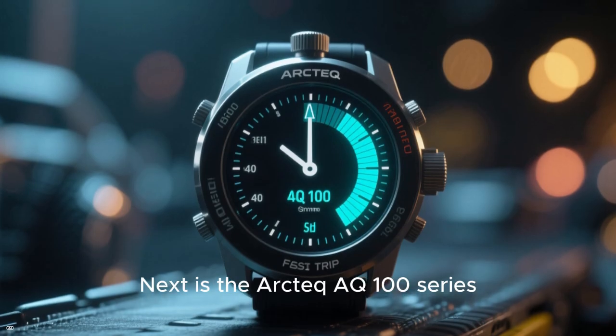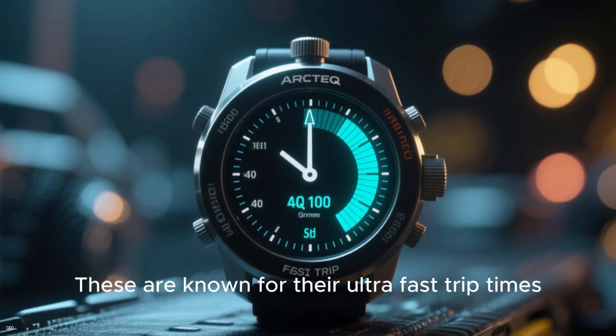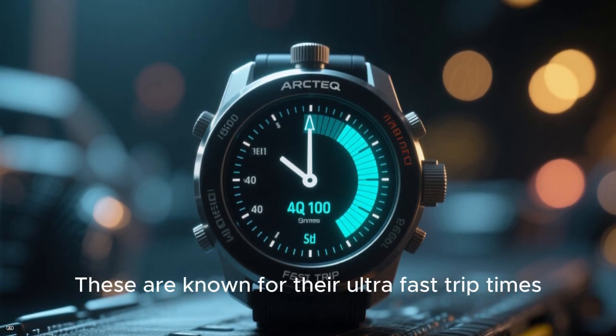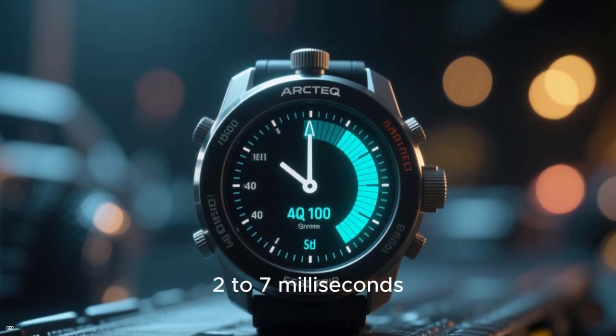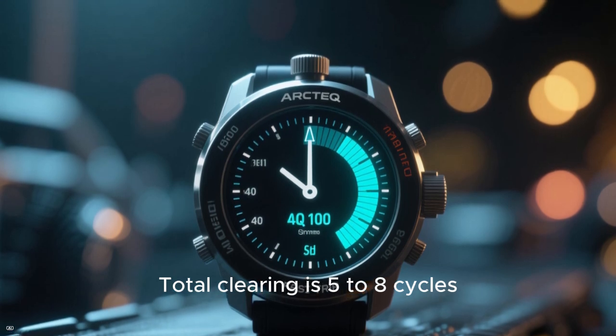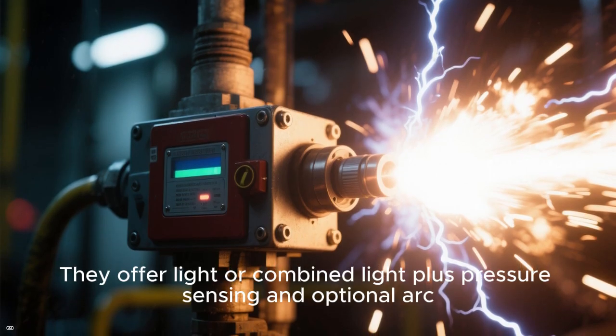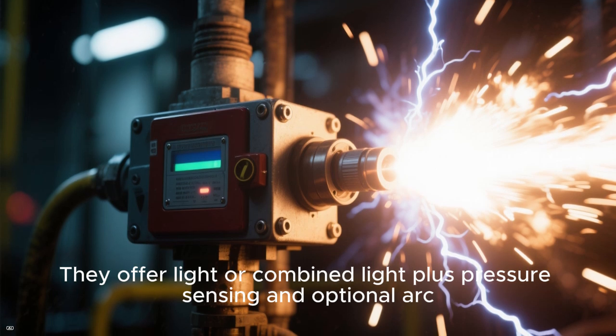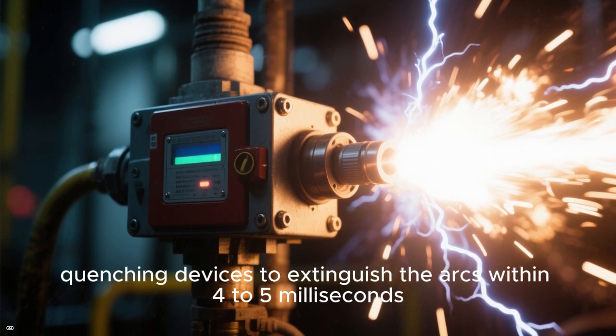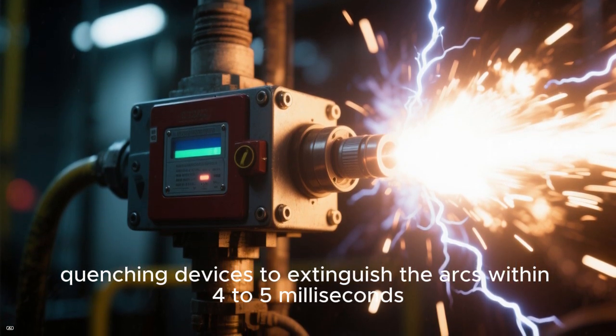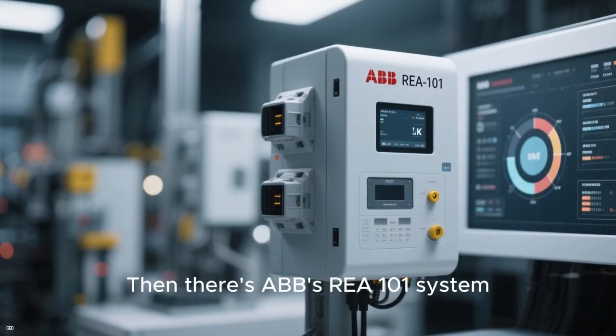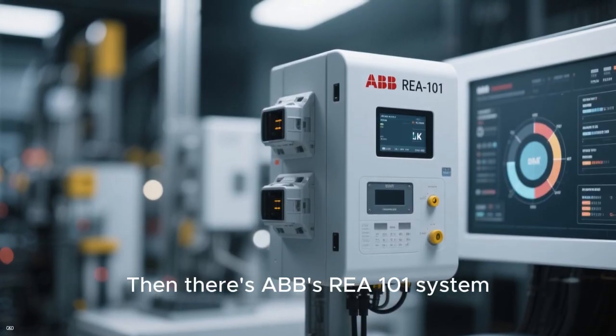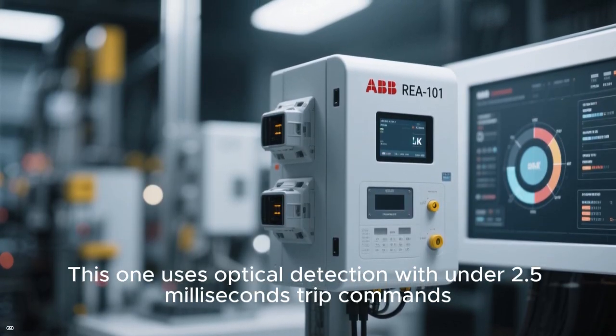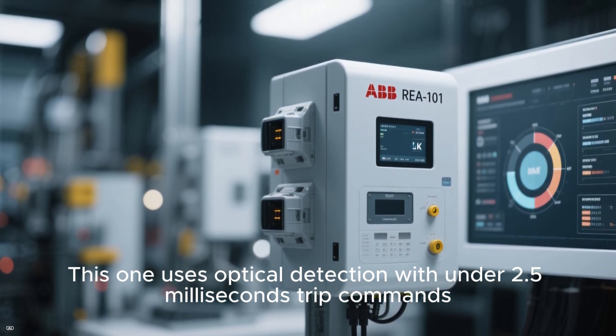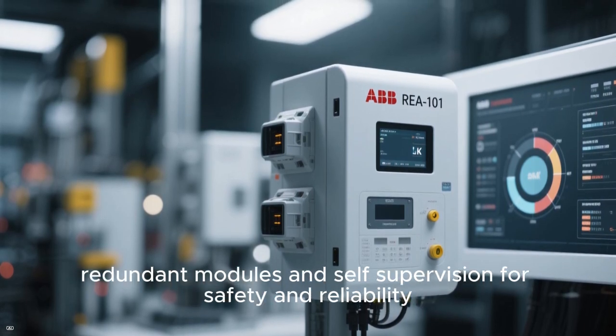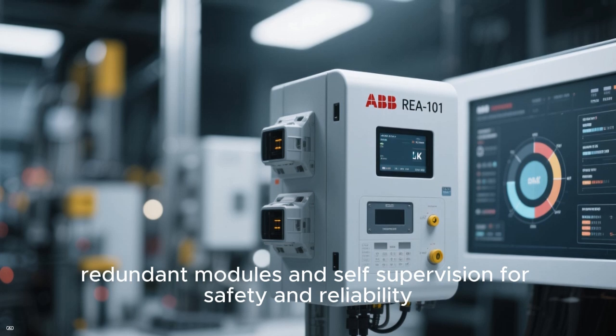Next is the Arcteq AQ100 series. These are known for their ultra-fast trip times, 2 to 7 milliseconds. Total clearing is 5 to 8 cycles. They offer light or combined light plus pressure sensing and optional arc quenching devices to extinguish the arcs within 4 to 5 milliseconds. Then there's the ABB REA 101 system. This one uses optical detection with under 2.5 millisecond trip commands, redundant modules, and self-supervision for safety and reliability.